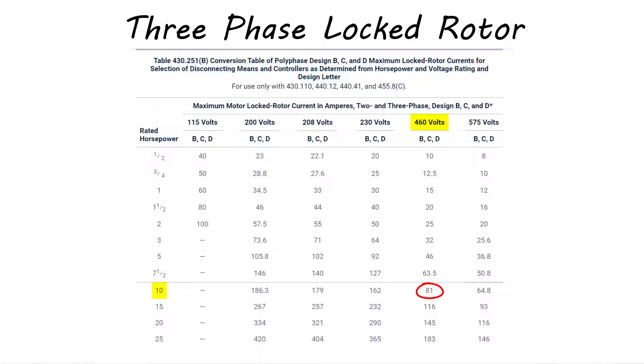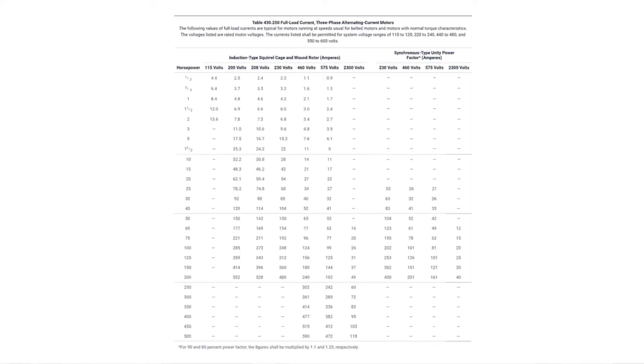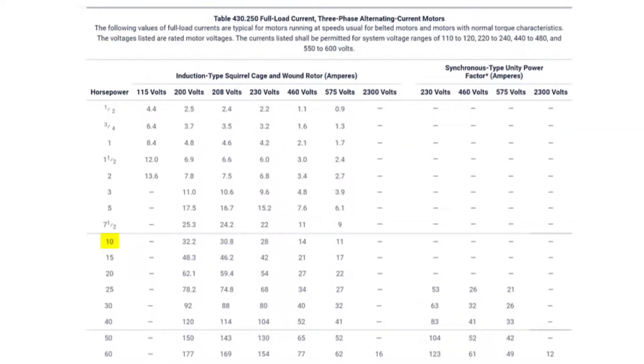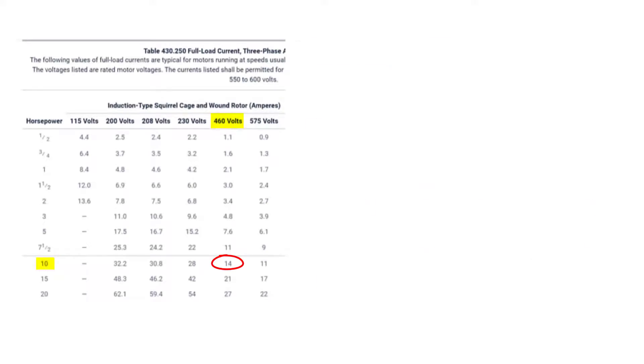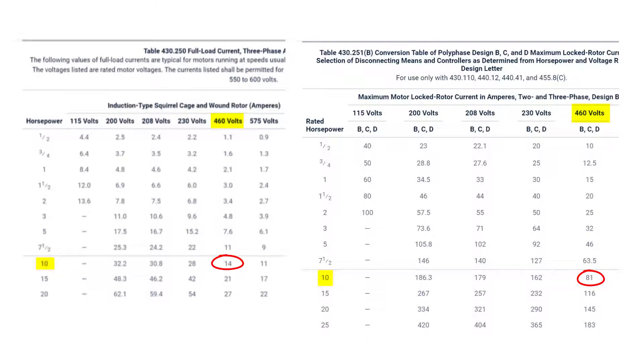If they're asking for a locked rotor, they're looking for these tables, not the other. Now, the reason why that might be confusing, remember that 10-horsepower at 460 volts is 81. Let's go back to our 430.250 table. Let's find that same motor. 10-horsepower fed with 480 volts. What is a full-load current? 14. So what I'm saying is this. On a 10-horsepower motor, you've got 14 for full-load current and 81 for locked rotor current. Make sure you're on the right table. If they ask for a locked rotor, don't go to the full-load current table. If they ask for a full-load current, don't go to the locked rotor table.